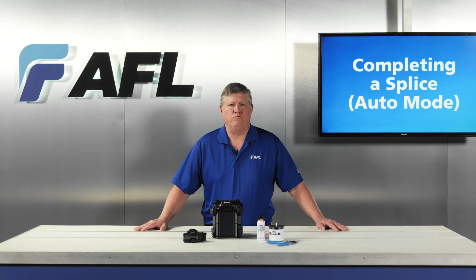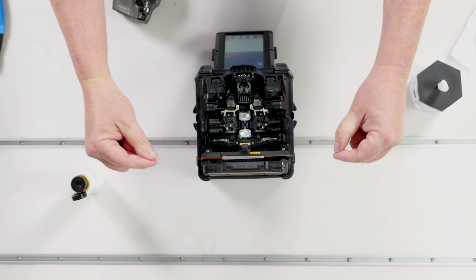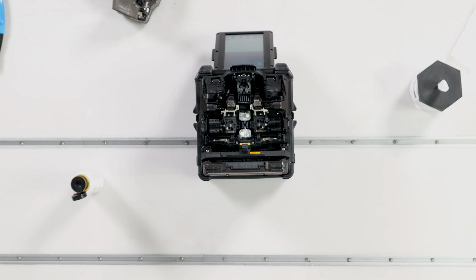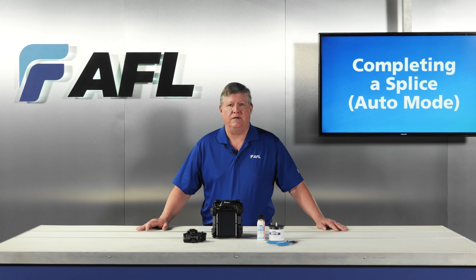After heating, remove the protected splice and place it in a safe area to cool. The sleeve will be hot. Avoid handling it until it cools completely. A properly heated sleeve should be evenly shrunk, straight, and firmly bonded around the splice.